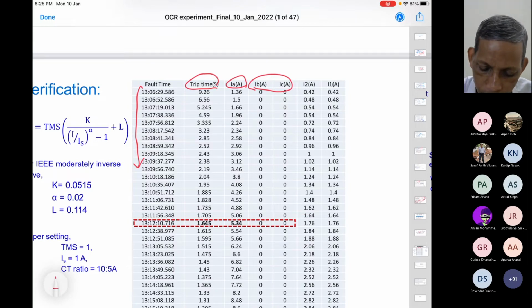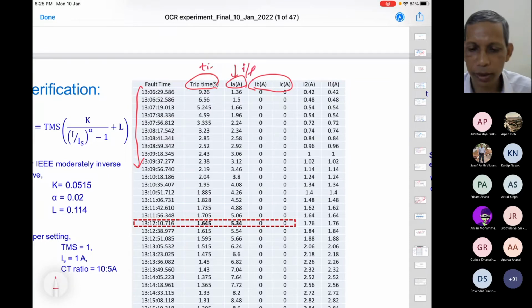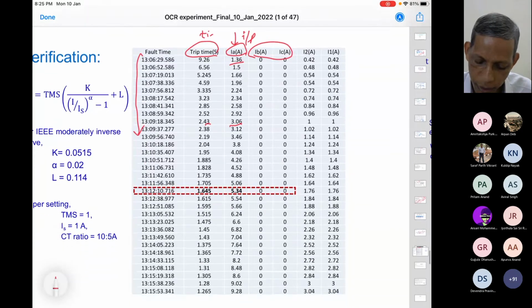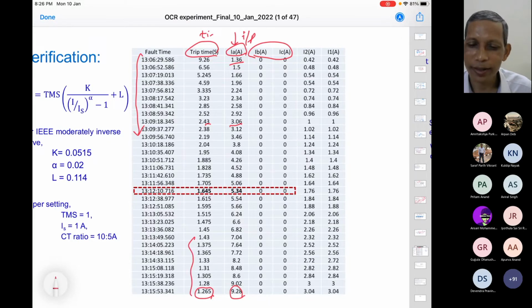So this is the current input, and this is the corresponding time we are getting for the decision time. If you see here, for 1.36 the time is 9.26. For 3 ampere, it is 2.43, much lower. If we go down, the current keeps increasing, 9.28, and the corresponding time is 1.265, which is very close to 1.3. This is the minimum time. Inverse, definite, minimum time. So this is the minimum time we are talking about. Okay?